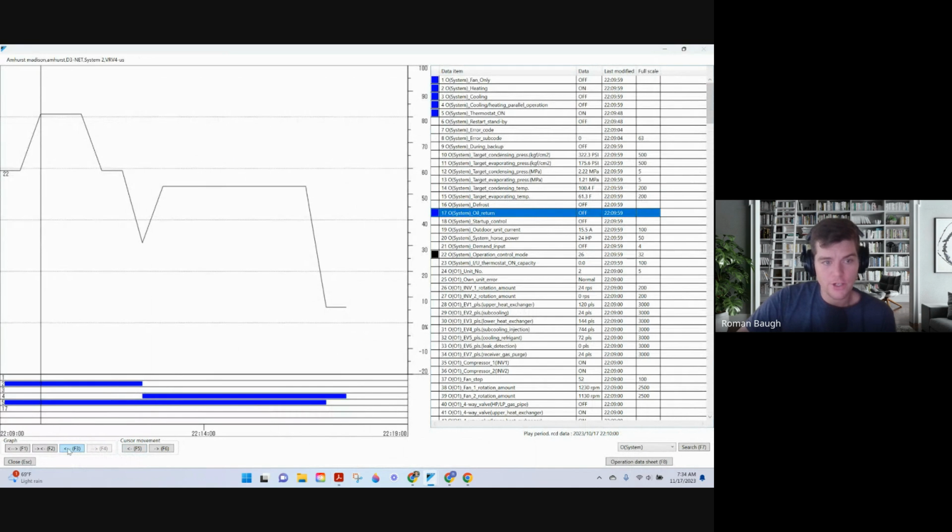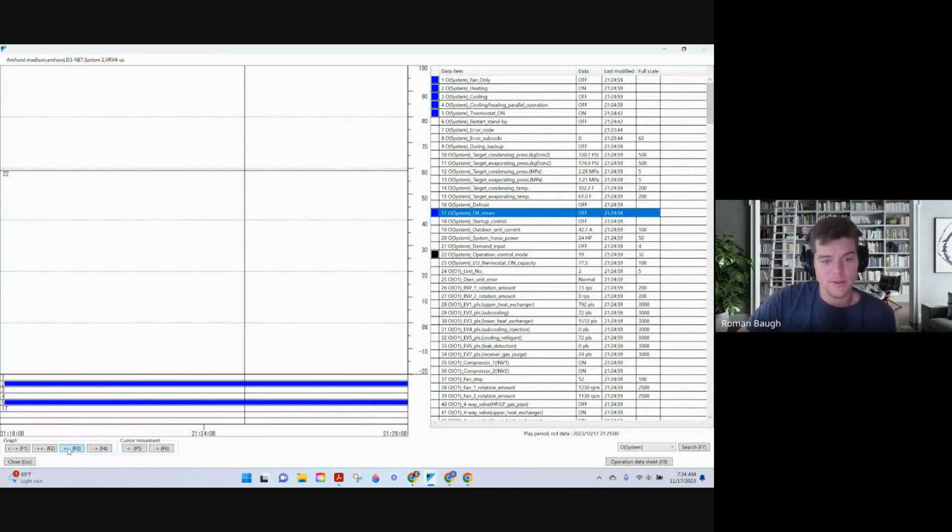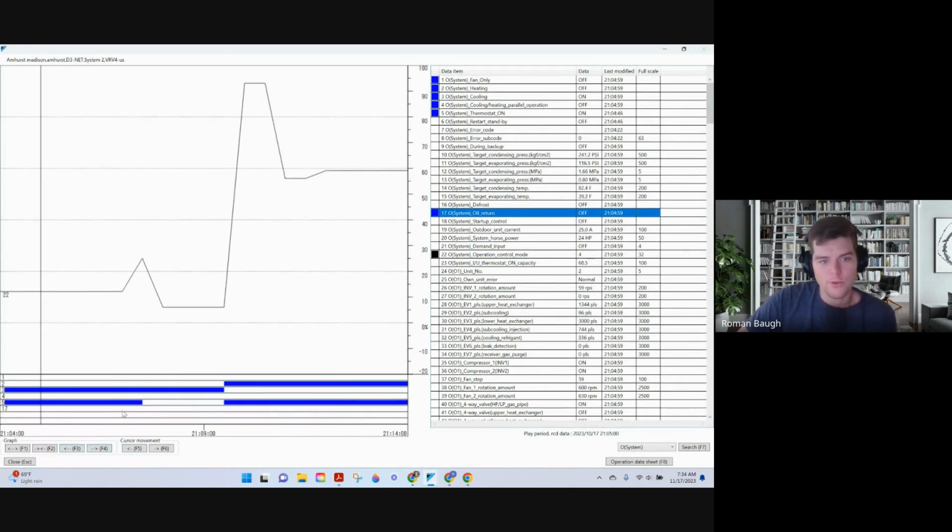All of this information is here, guys. It's always been here to help you troubleshoot systems. When you can get an exact start and stop time, you know that the system should be ramping its compressor up, shutting its indoor expansion valves, pumping itself down. You might see that the pressure might dip down low in these regions. That's all normal control. It'll allow you to look at the data that you have in front of you.